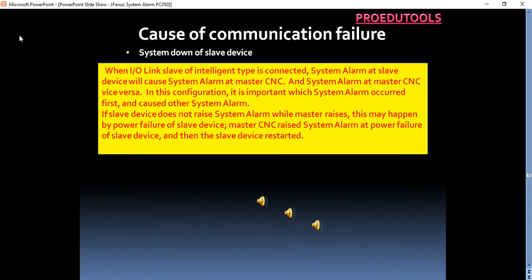System down of slave device. When IO link slave of intelligent type is connected, system alarm at slave device will cause system alarm at master CNC, and system alarm at master CNC vice versa. In this configuration, it is important which system alarm occurred first and caused other system alarm. If slave device does not raise system alarm while master raises, this may happen by power failure of slave device. Master CNC raised system alarm at power failure of slave device, and then the slave device restarted.